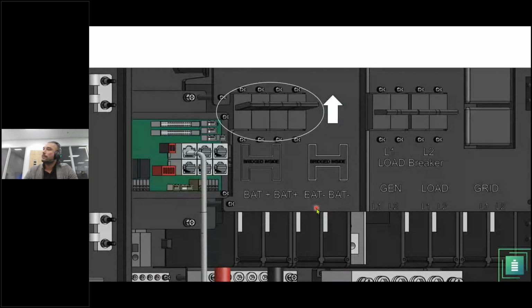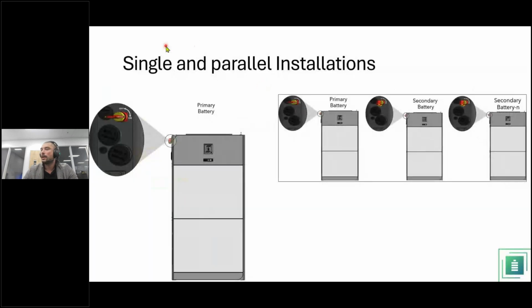For commissioning, flip the breaker of the MV first, the battery breaker on the MV first, and then we're going to turn on the switch on the eForce. If you have a standalone like this, turn this switch. If you're having parallel systems, then you only turn on the master, which is always the battery that communicates directly to the MV. So I turn this on.